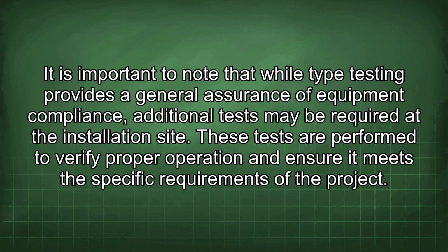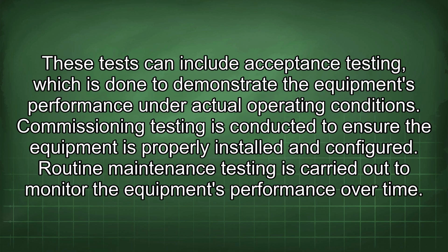It is important to note that while type testing provides a general assurance of equipment compliance, additional tests may be required at the installation site. These tests are performed to verify proper operation and ensure it meets the specific requirements of the project. These tests can include acceptance testing, which is done to demonstrate the equipment's performance under actual operating conditions. Commissioning testing is conducted to ensure the equipment is properly installed and configured. Routine maintenance testing is carried out to monitor the equipment's performance over time.